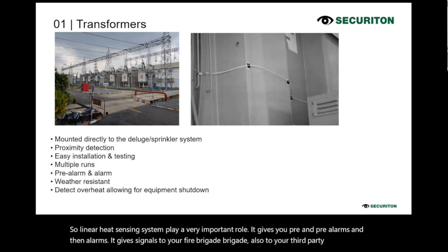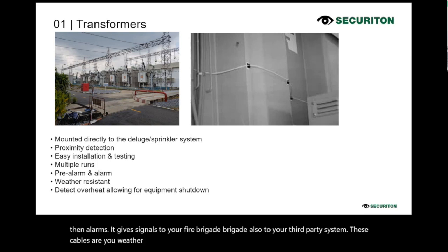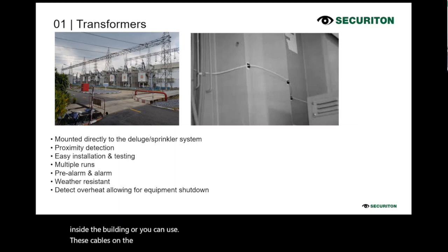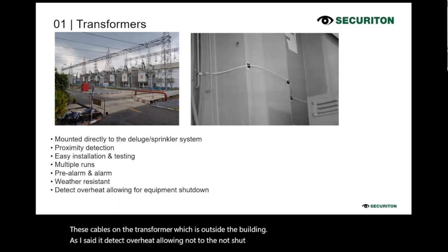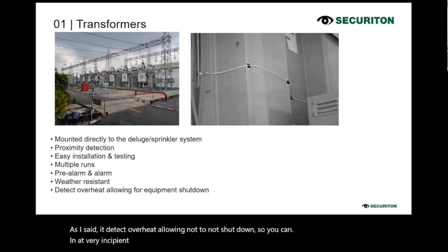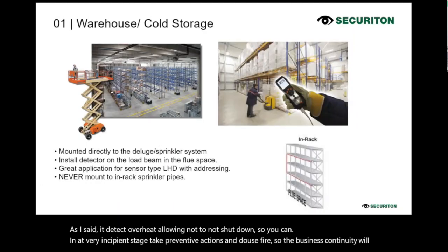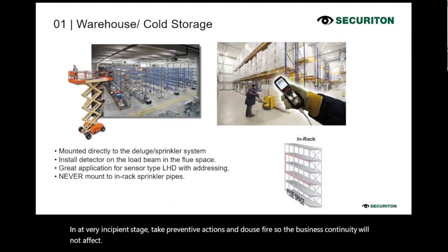These cables are weather resistant. You can use them for internal transformers which are inside the building, or you can use these cables on a transformer which is outside the building. As I said, it detects overheat, allowing not to shut down. So at a very incipient stage you can take preventive actions and douse the fire, so business continuity will not be affected. Another application is your warehouse.